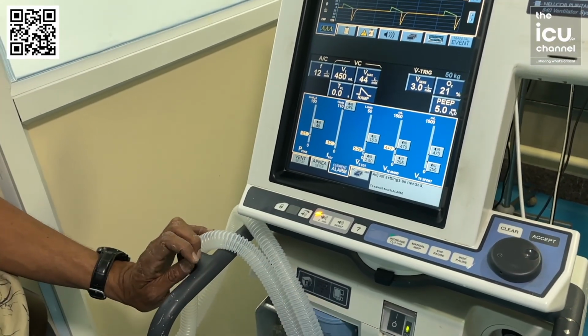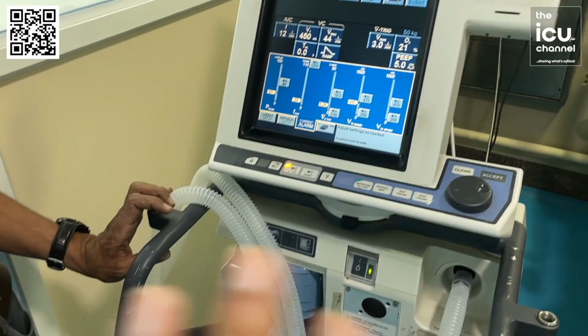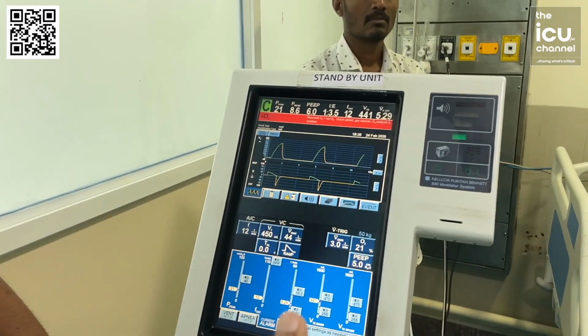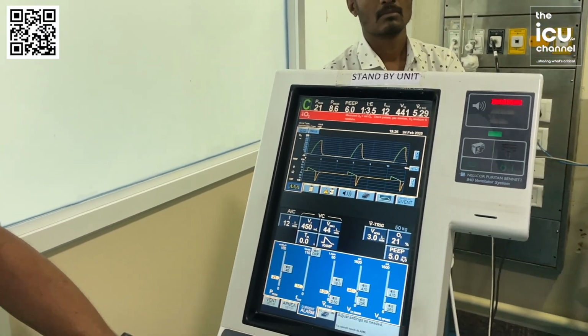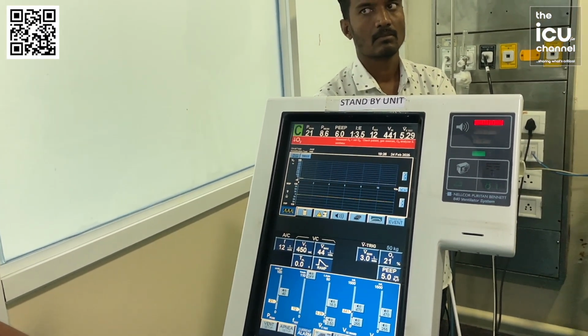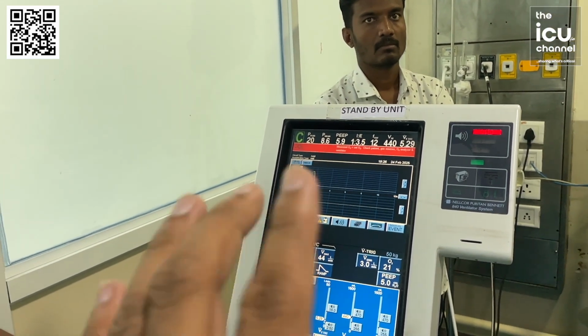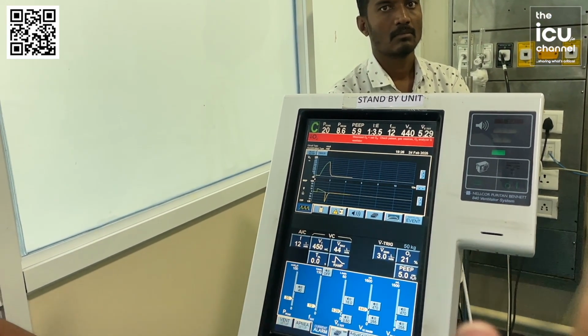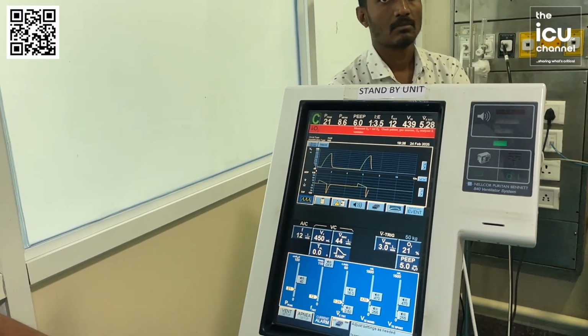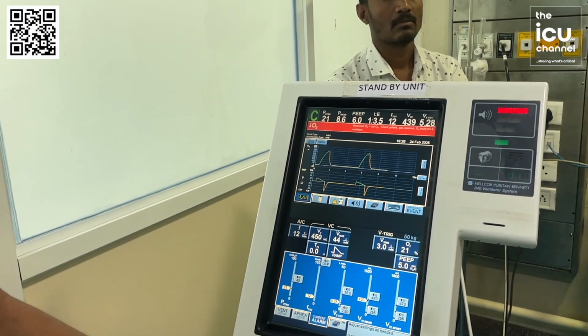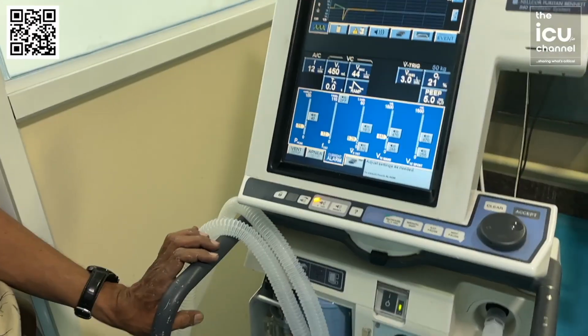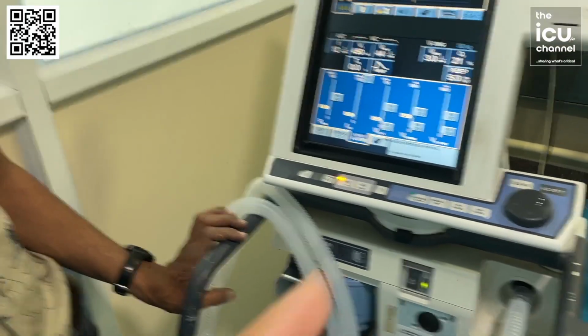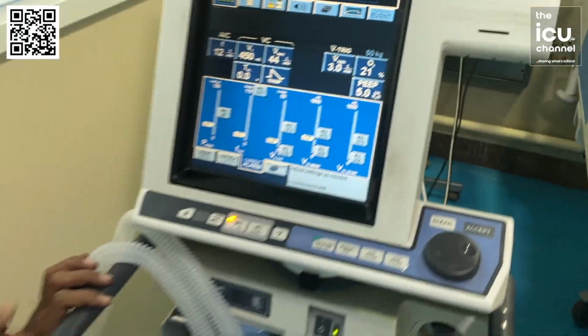And once they are going into the mixer, there is again a safety valve. So it will check again the tidal volume and the pressure. The safety valve's function is, suppose we have set 10 breaths on the ventilator, it will only open up when we want the inspiration to go inside. In between, in the expiratory phase, it will close. It will not allow the oxygen and the air to go into the inspiratory side. That's fine. And the oxygen sensor is also there, which will sense whether we are sending the correct amount of FiO2 or not.